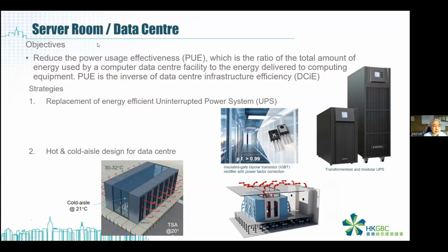And regarding the server room, we can use high efficiency UPS systems with very good power factors. And we can also use hot and cold aisles for the data centers. Here you can see that the cold aisle should be enclosed. Inside the cold aisle, the air temperature is around 21. Outside it is around 30, so there is a great temperature difference between the cold aisle and hot aisle. This is the correct design.